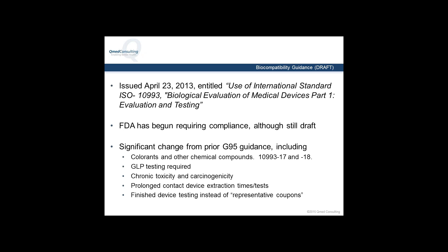Some of these are extraction methods and very strong solvents, things that a device arguably would not see in normal human use. Some of the extraction times have changed. Some of the testing has changed. Back in the old days with pacemakers, you could take a pacemaker can and just take a piece of the can and run that through your biocompatibility test. Now companies are being required to use full devices instead of what was called coupons before. Obviously that changes the cost involved from a sample standpoint in having to run the biocompatibility screen.